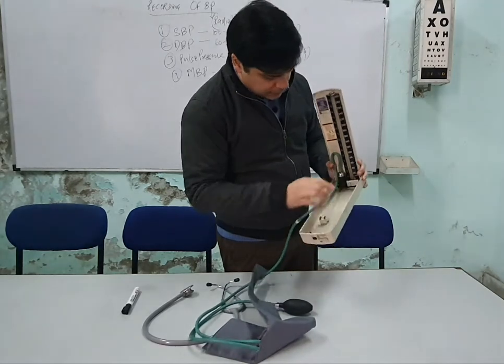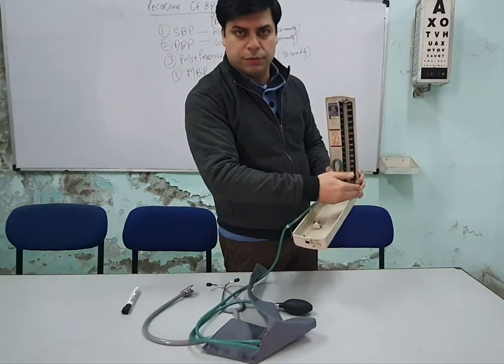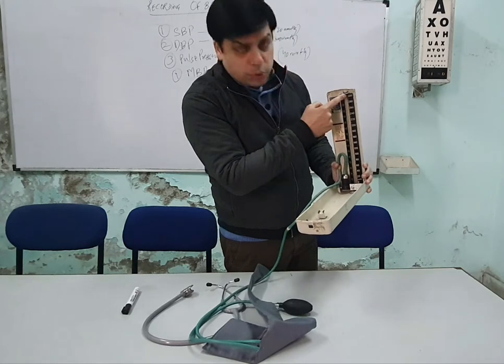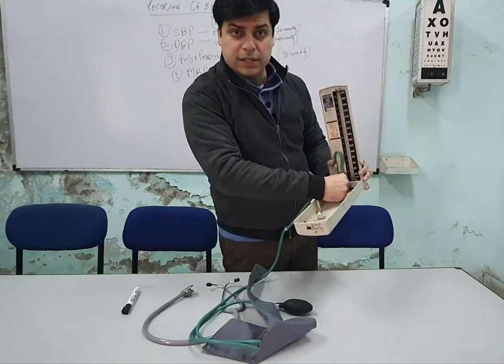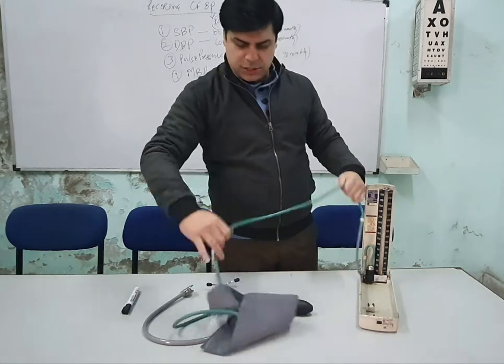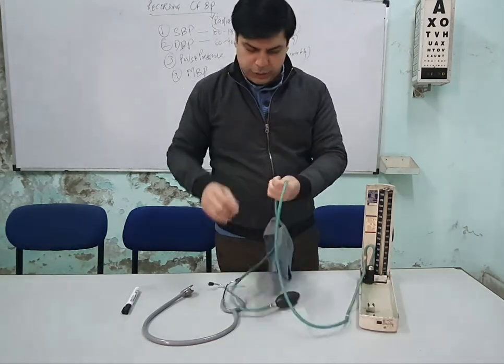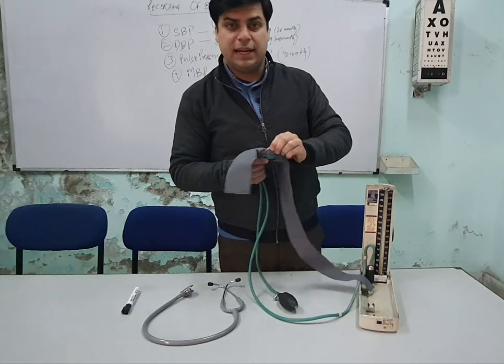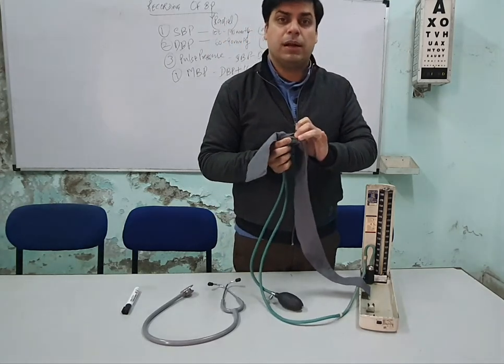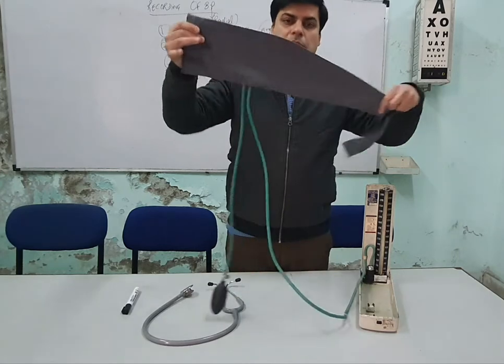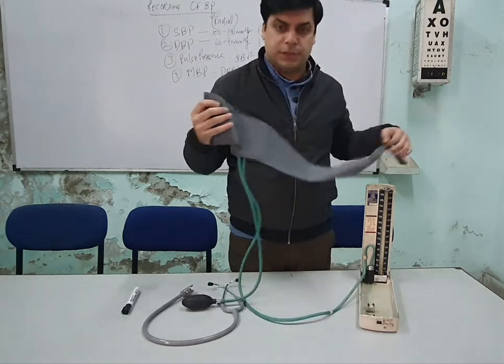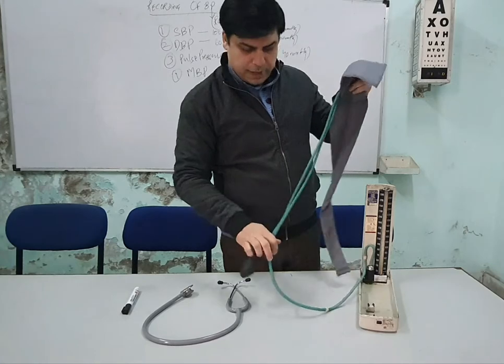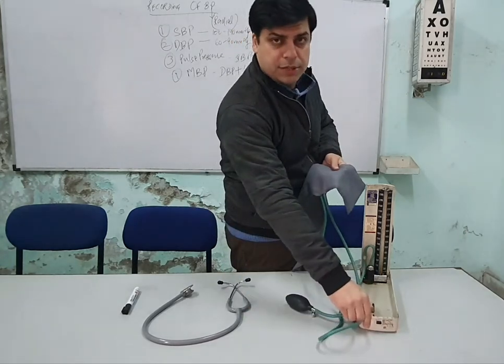On the sphygmomanometer, there is a lock for on and off to the manometer tube. It has a graduated glass tube going up to 300 mmHg, a mercury reservoir, and a rubber tube connected between them. On the other end there is an inflatable rubber bag covered by a cloth piece called the Riva-Rocci cuff. The cuff size used in adults is 24 by 12 cm.